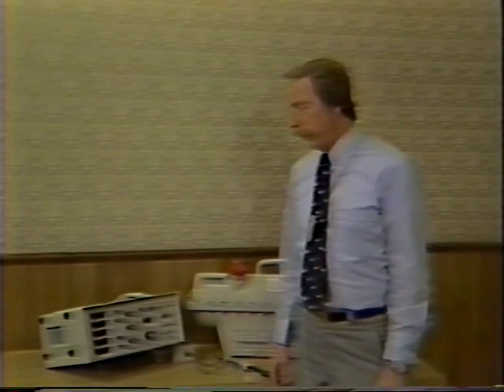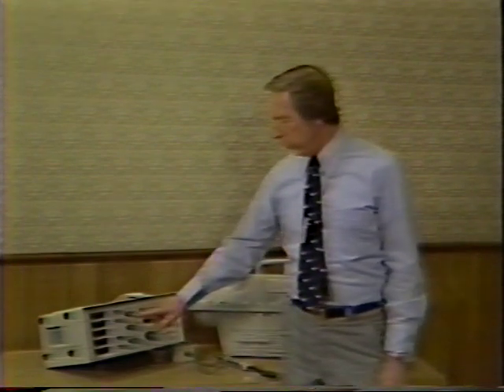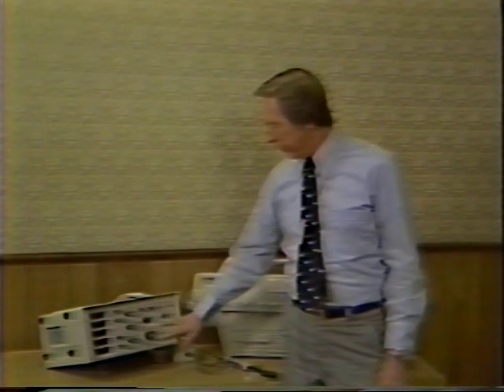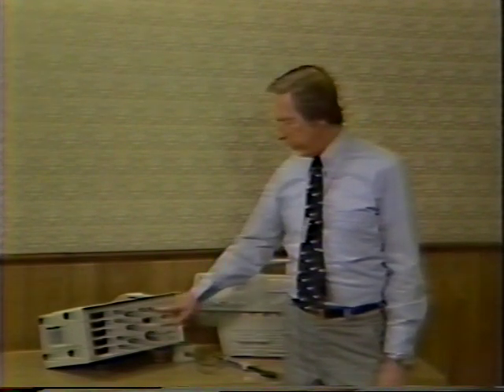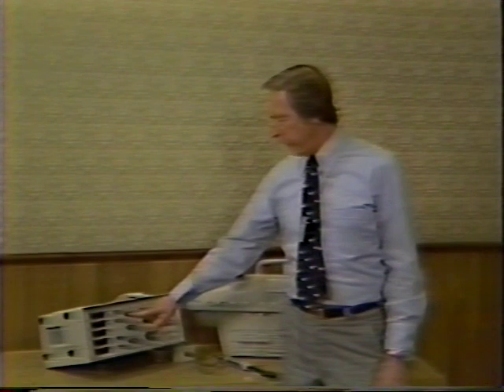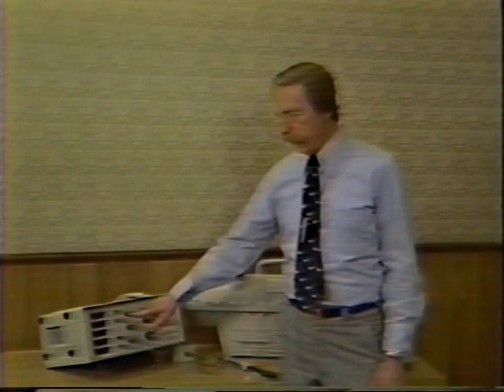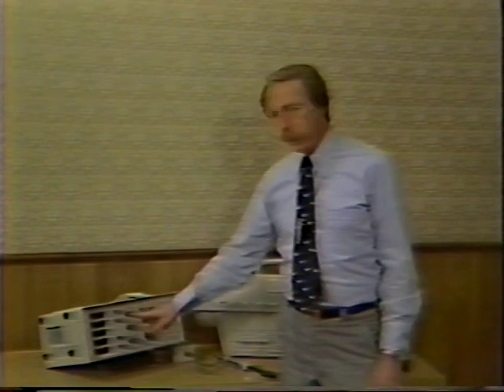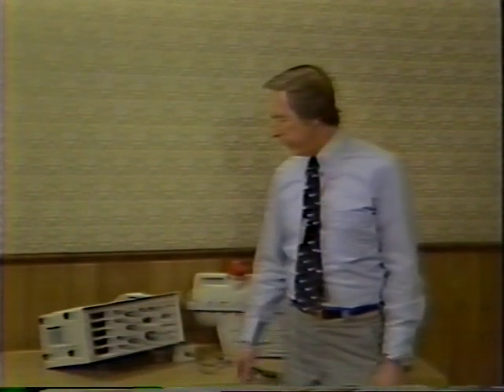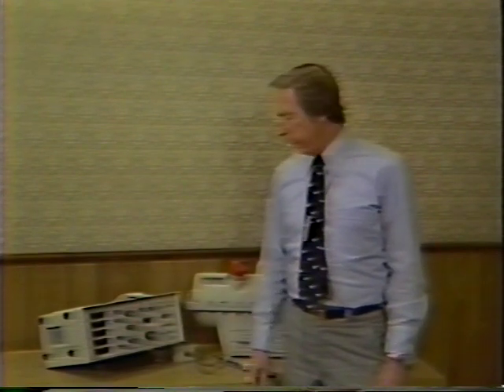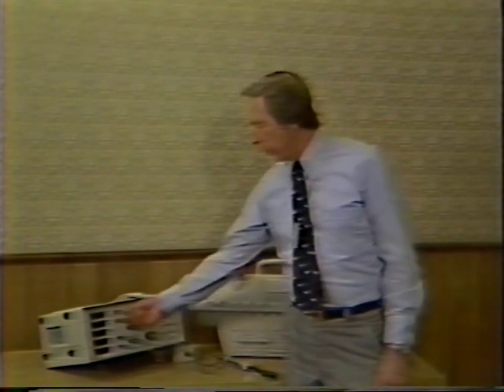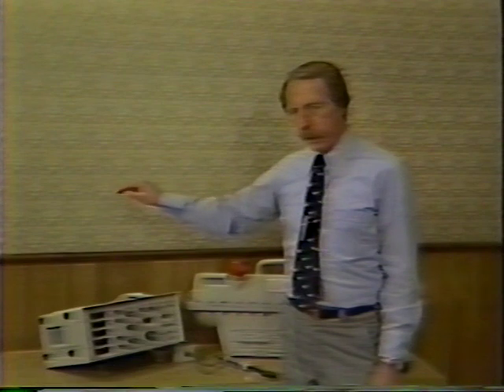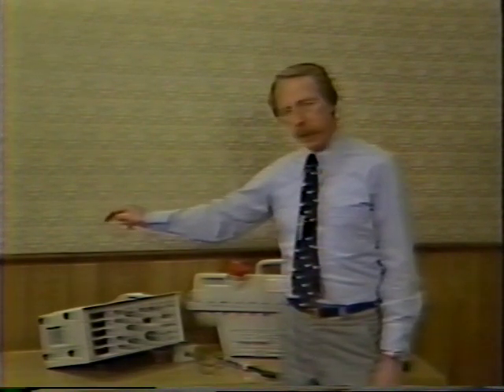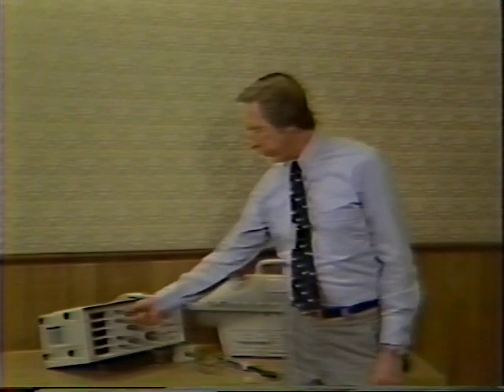We now move to the central panel of the digital Dynalyzer. We have three controls that are interrelated: the trigger source, the trigger level control, and the trigger mode switch. In the trigger source, we have 5 positions, or 5 different ways that we can trigger the digital clock in the Dynalyzer. The first one is kVp, which will be used by most of the people. We also can trigger from mA, assuming it's a constant potential equipment, or we can trigger from the external trigger in a laboratory setting. In this case, you would insert the triggering signal into the coaxial connector on the back of the digital display. On the Dynalyzer 3, we added 2 additional positions.